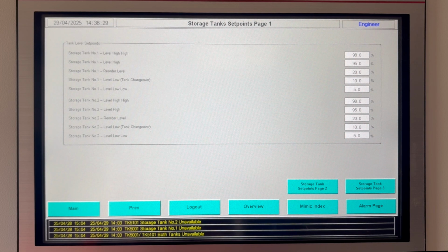At 20%, this amount could be taken immediately with no operational issue and would raise the level to around 92%. In reality, the tank is likely to have dropped further before delivery is taken, to around 10%, allowing for a greater margin of safety and avoidance of nuisance alarms. Low level. This was set at 10% at commissioning and is at the point at which the bulk tank switches duty. Changeover. At this level, the tank will have approximately 1,500 litres remaining.